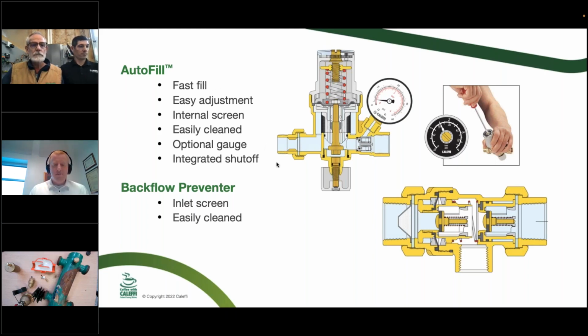These particular products are very common on everything from residential to commercial type applications. The idea is that it's basically like a pressure reducing valve that maintains a specific pressure downstream to make sure that system is full of water. And so again, you start bleeding off air or blowing down dirt separators. A device like this is actually going to bring fresh water into the system. Now, it's kind of a double-edged sword. You got to think about that.